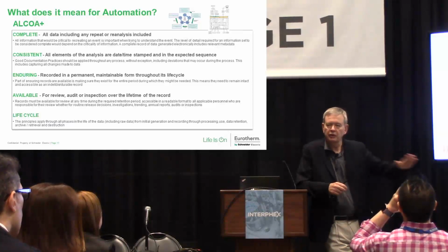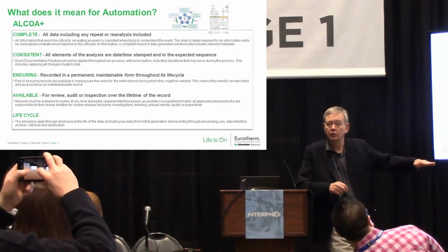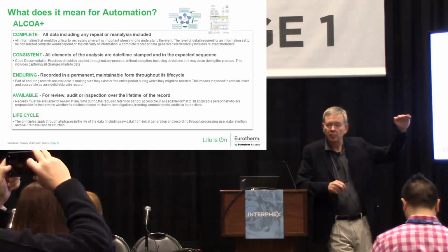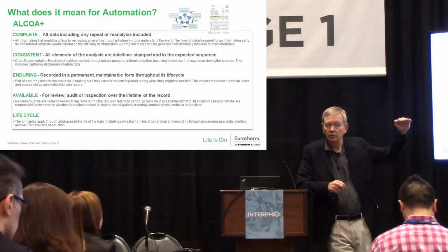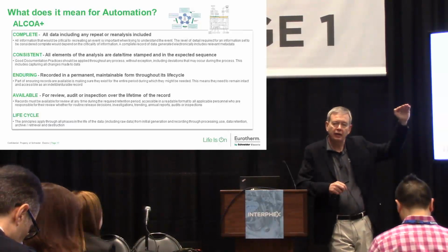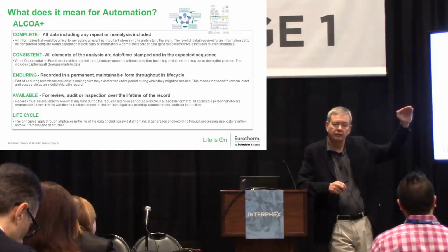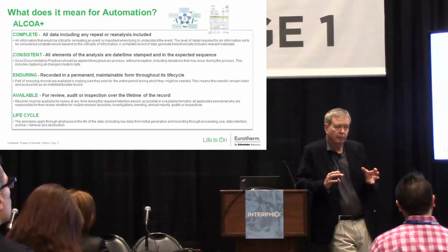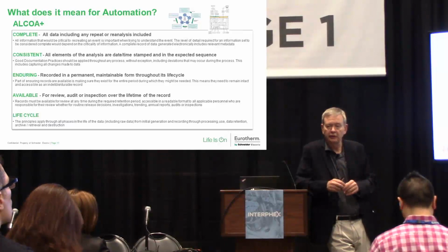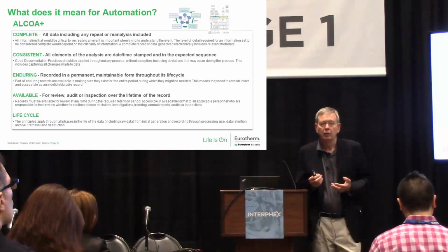A lot of the instrumentation on that lower level of the system architecture will have memory storage within it. A lot of times it's flash memory. Sometimes it can be quite a bit of flash memory. The devices above that, FTP file server, maybe that's the place you save the information. Maybe you want to do that in a secondary way, maybe a secondary FTP file server. Those things are all good, but you have to make sure that however you're recording the data, it's very permanent. And not only permanent, but available.